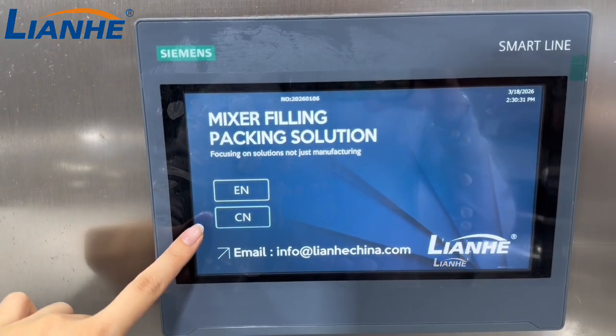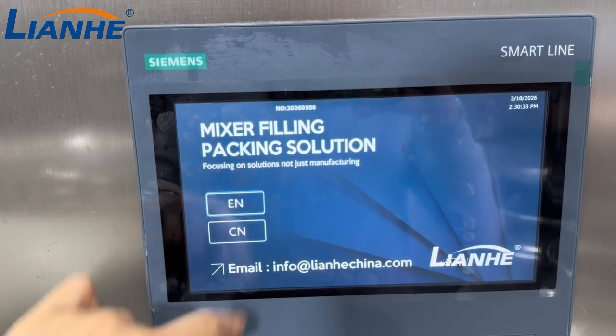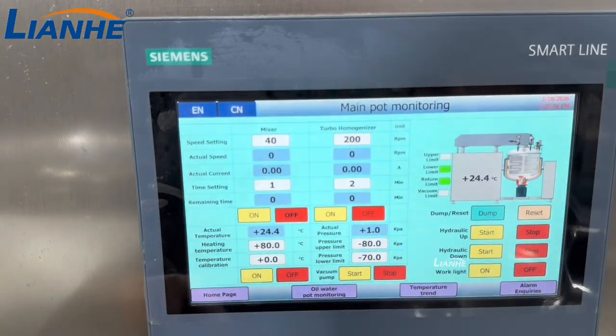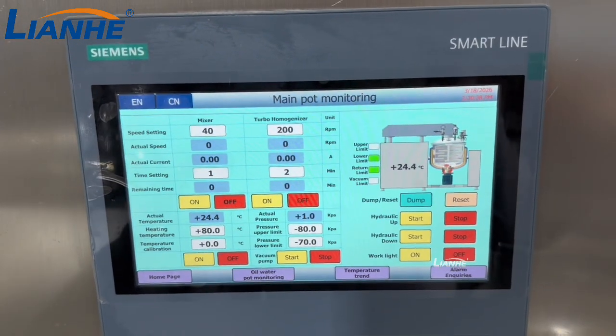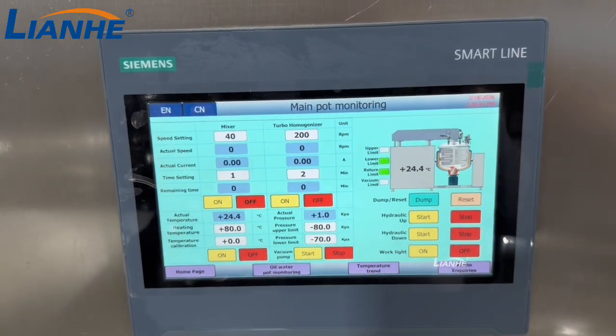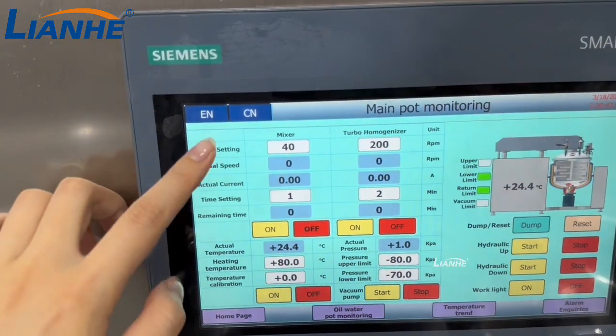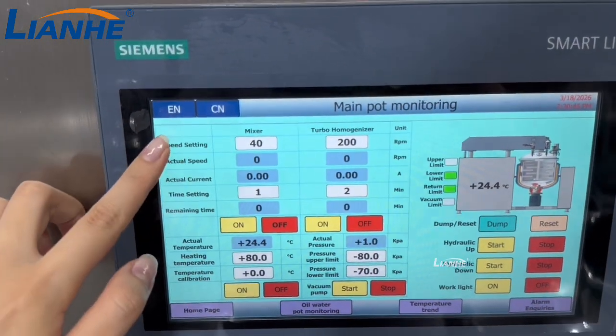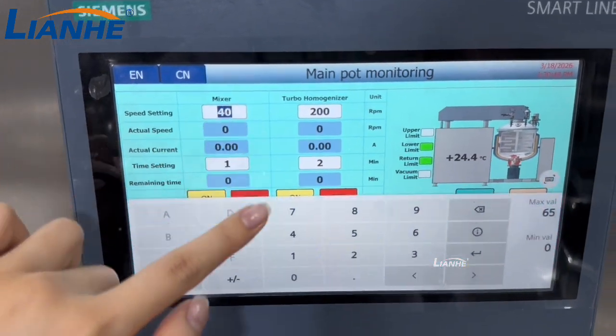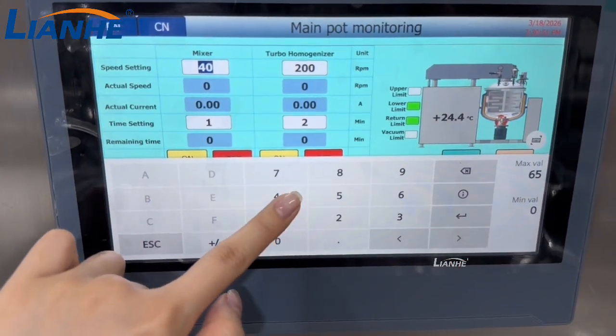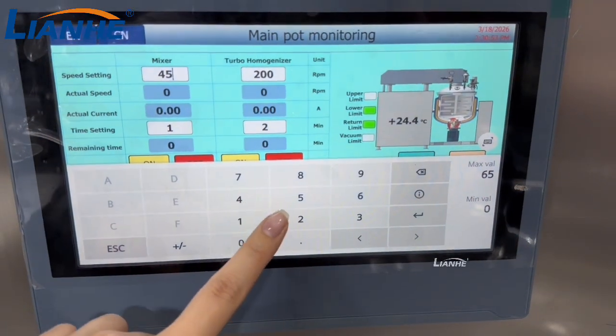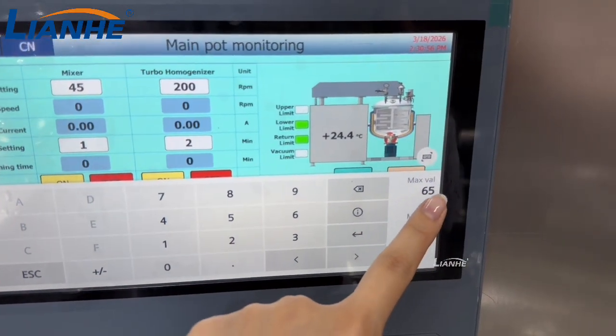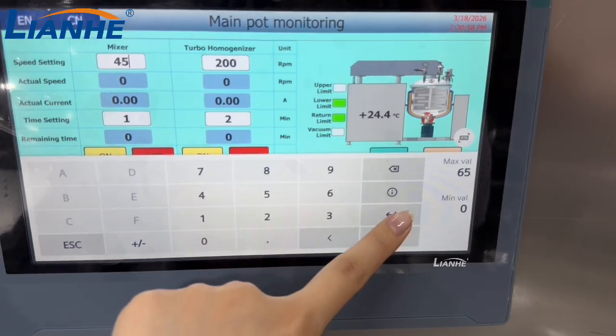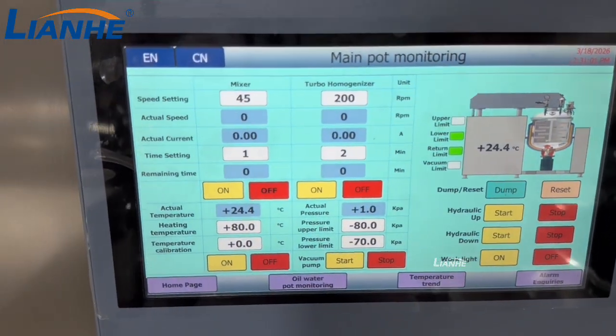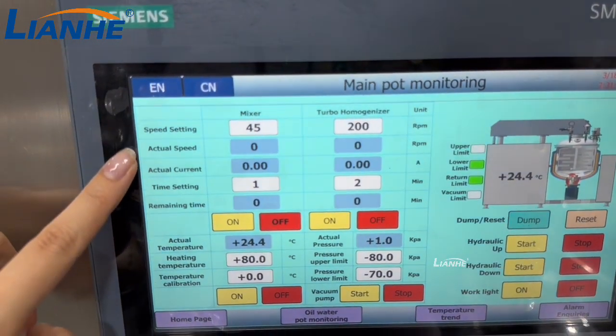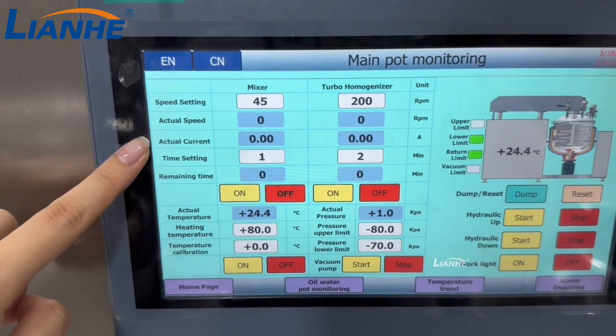And then let's check the screen. There are two languages you can choose. We can choose English for reference. And then this is the main pot monitoring for the main tank machine. And then let's check this one, the mixing function. You can set the speed here, like we want 45 speed. Put it in, and then this is the maximum speed you can select, and then push here. Then we can set the speed, and then this is the actual speed display, the actual current display.